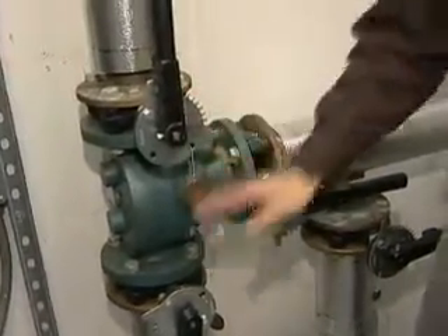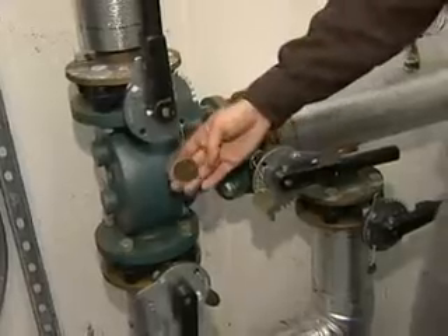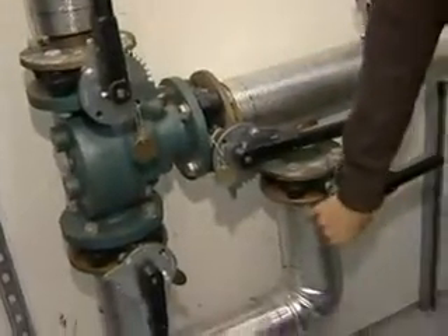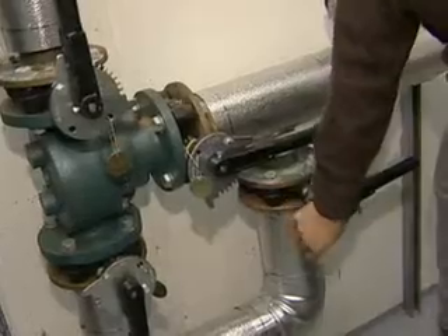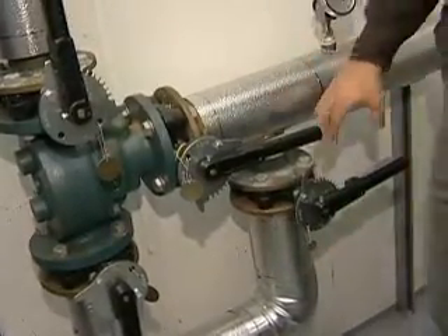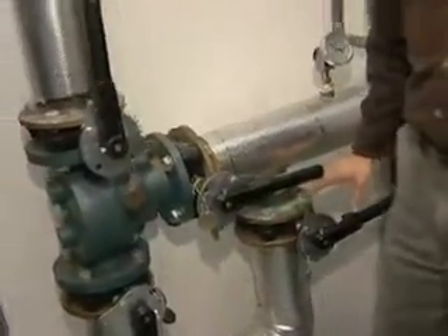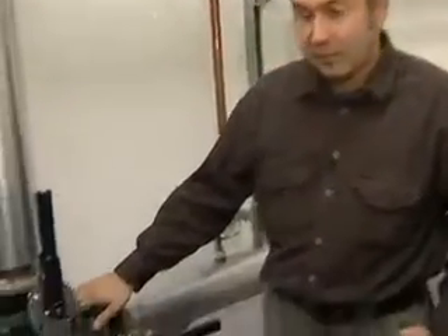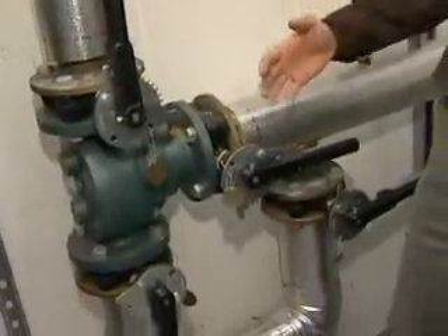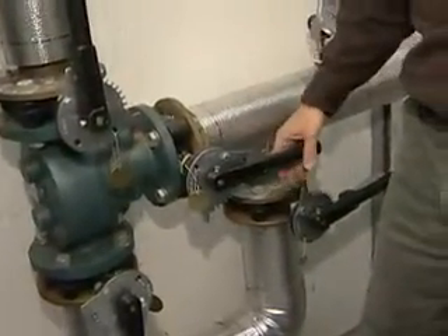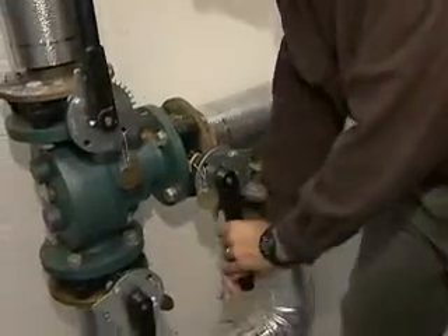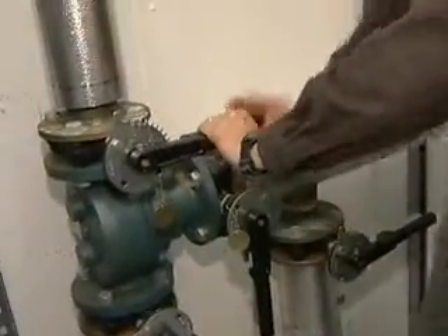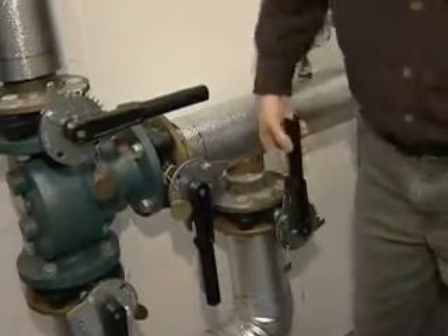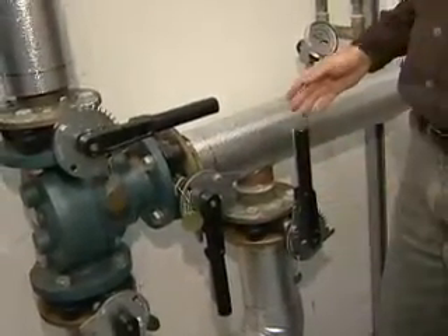And the three valves are provided to isolate it if it needs to be serviced. These are all normally open. Then over here we have a normally closed bypass valve, and this will typically be labeled with a tag that actually says normally closed, open only on high coolant temperature alarm. So if this mixing valve were to ever fail for some reason and you couldn't get the coolant to go through the radiators, what you would have to do is come in and valve off this one and then open the bypass valve. And what that'll do is get full flow going through the radiators and give us full cooling.